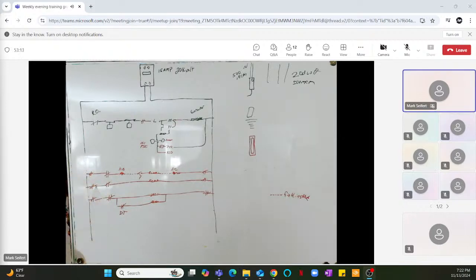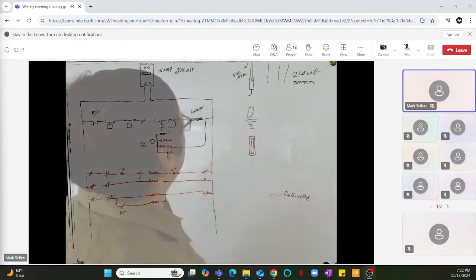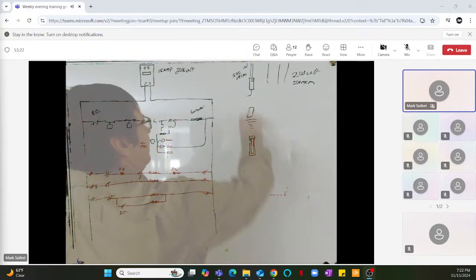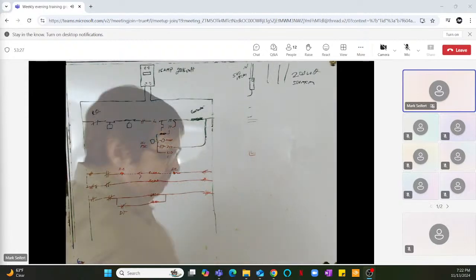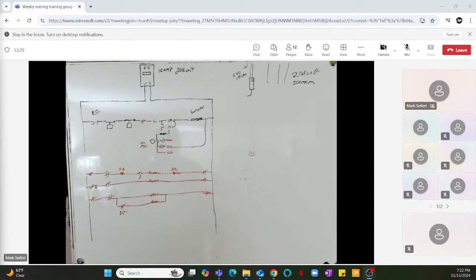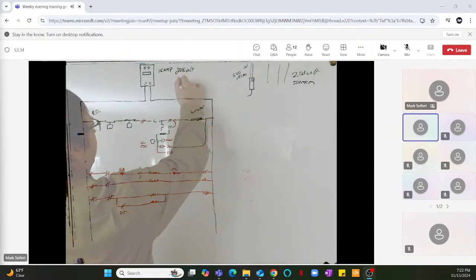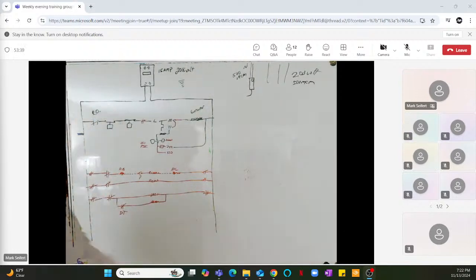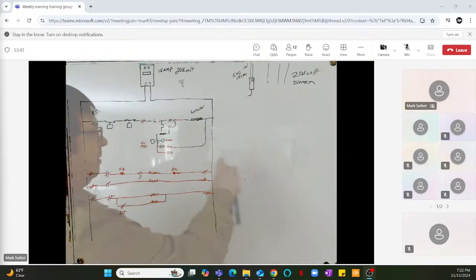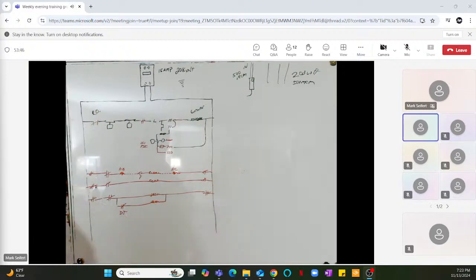Are there any questions on store heat? Are any of you guys having trouble with the store heat? Like the heater's working, but it doesn't seem to be making it down to the sales floor? I have one store where the high limit switch keeps tripping, but only every so often. I just pop in and reset it, and then it's back online.